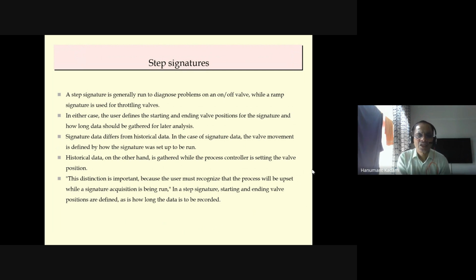This distinction is important because the user must recognize that the process will be upset while signature acquisition is being run. So you will come to know it takes time. In a step signature, starting and ending valve positions are defined, as is how long the data is to be recorded. Earlier it was, suppose, 1 second, then it is taking 1.5 seconds like this. And if this 0.5 second difference is there, that will affect your process.